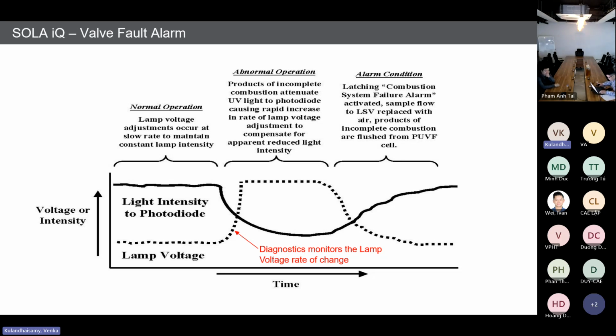Whenever the valve fault alarm occurs, the system will automatically stop sample injection. That means it will not send any pneumatic signal to the injection valve, so the injection valve will not inject any sample. The sample will not go to the pyrolyzer, so it will be safe from over-contamination. Whenever the voltage is back to the normal operating condition, the valve fault alarm automatically disappears, and then the injection valve starts to inject the sample again. This way we are safeguarding our pyrolyzer and the PUVF bench assembly.